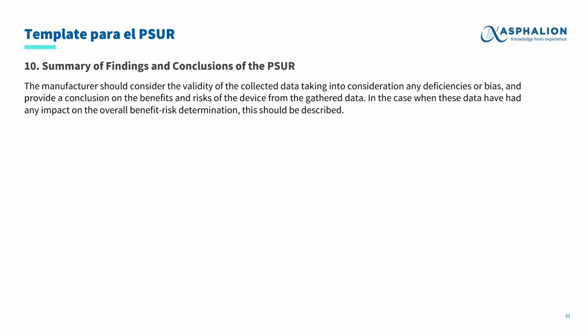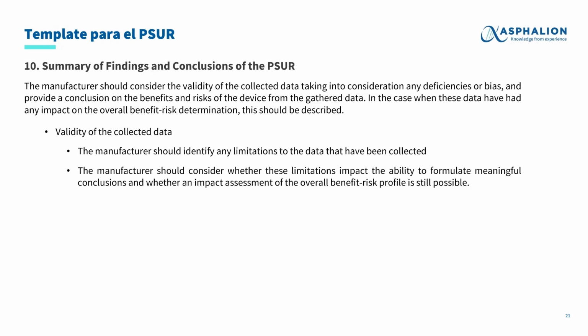To finalize with the PSUR, the last section should include a summary of findings and conclusions. Here, the manufacturer should consider the validity of the data collected, should also include a conclusion on the benefits and risks of the device, and add any action taken for safety reasons during the reporting period. So, starting with the validity of the data collected, the manufacturer should identify any limitation of the data that has retrieved from the reporting period, and consider if these limitations could impact or not the ability to formulate meaningful conclusions, and if an impact assessment on the overall benefit risk profile is still possible.